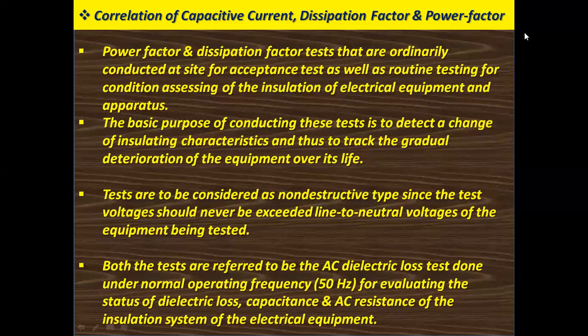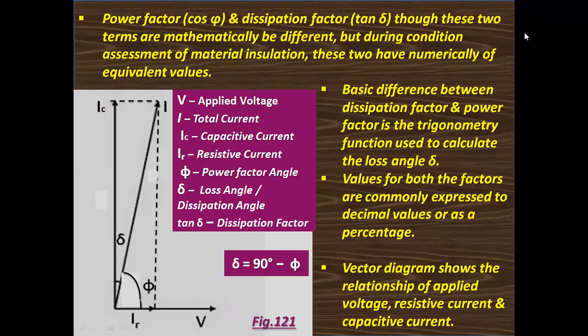Tests are considered non-destructive since the test voltages should never exceed line to neutral voltages of the equipment being tested. Both tests are referred to as the AC dielectric loss test done under normal operating frequency, that is 50 Hz, for evaluating the dielectric loss, capacitance, and AC resistance of the insulation system of the electrical equipment. Power factor, that is cos phi, and dissipation factor tan delta, though mathematically different, are numerically equivalent during condition assessment of insulation material.